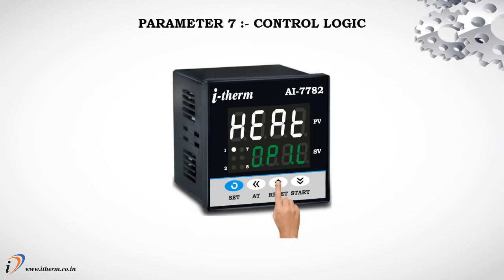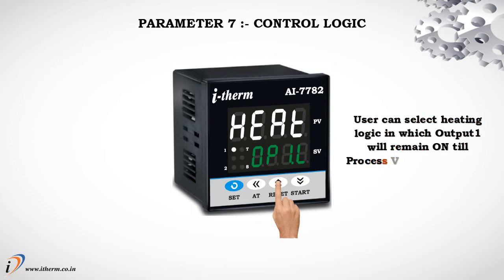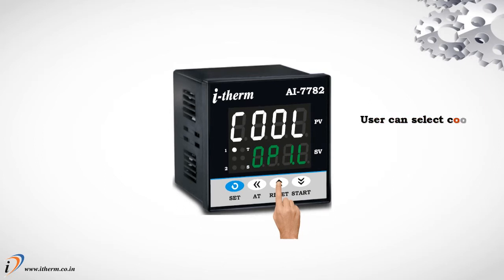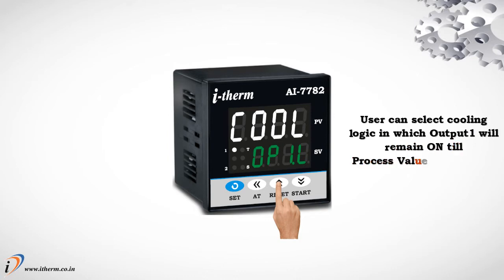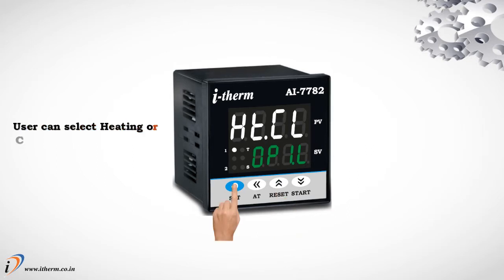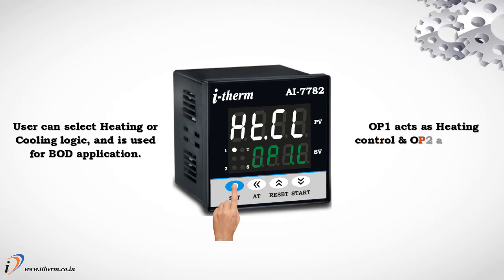Parameter 7, Control logic. The user can select heating logic in which output 1 will remain on until process value is less than set point. The user can select cooling logic in which output 1 will remain on till process value is more than set point. The user can select heating or cooling logic, used for BOD application, where output 1 acts as heating control and output 2 as cooling control.